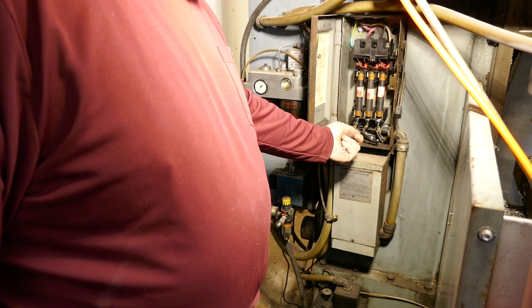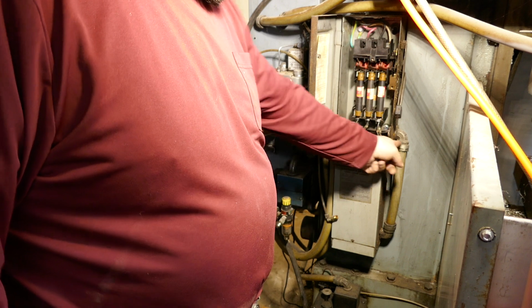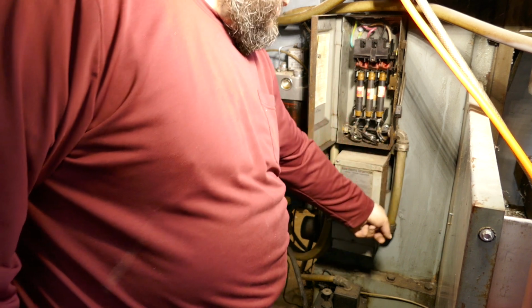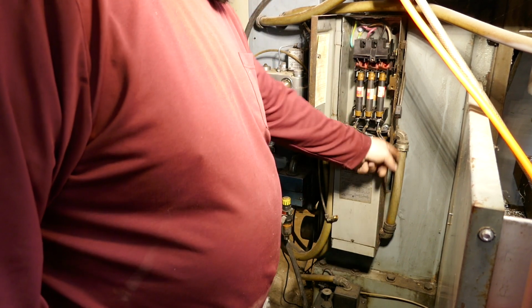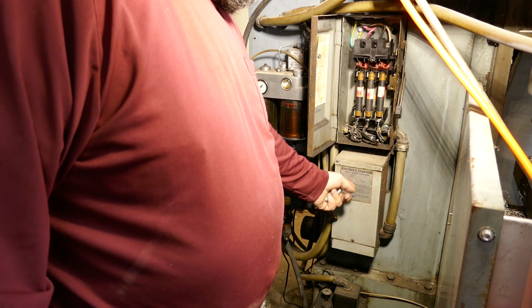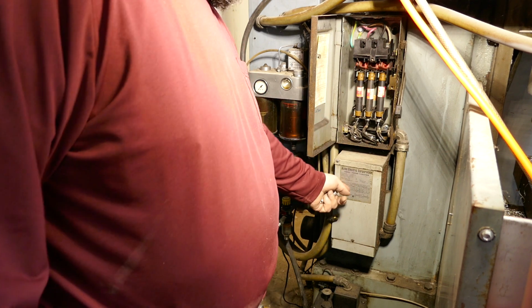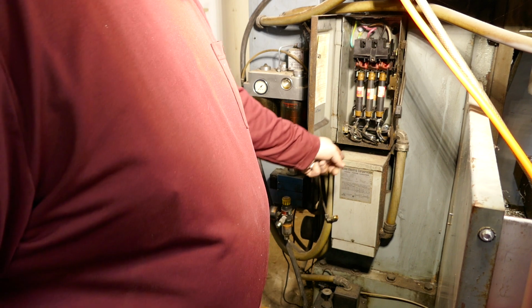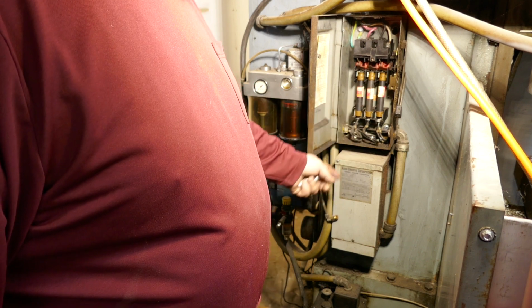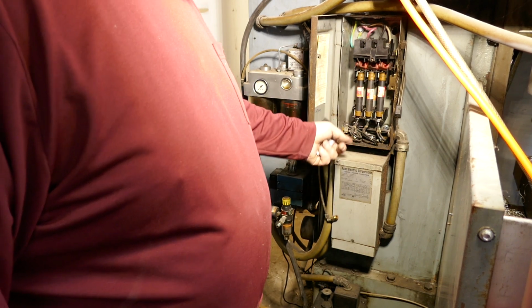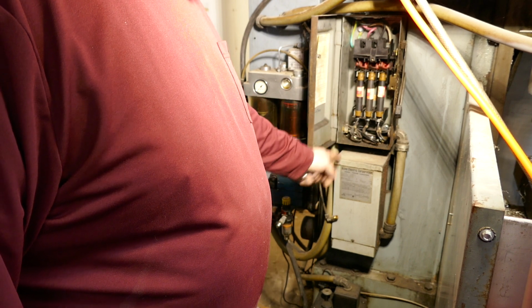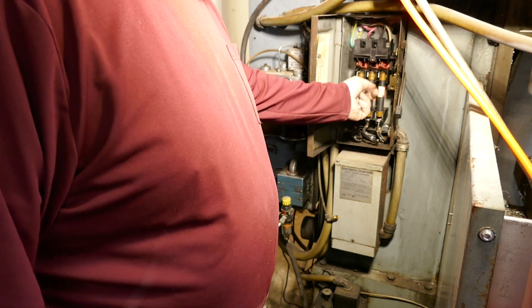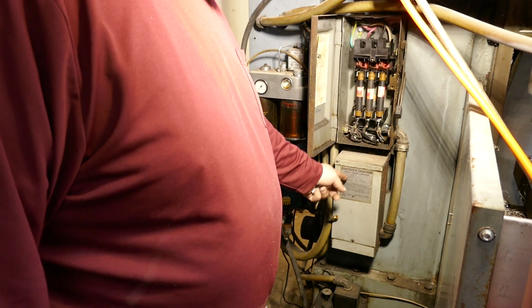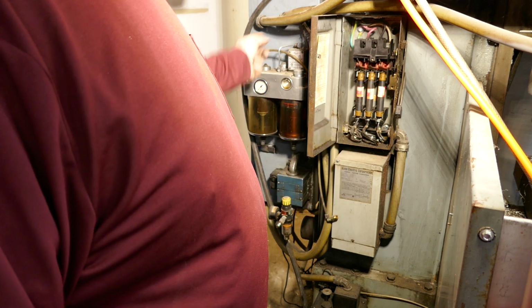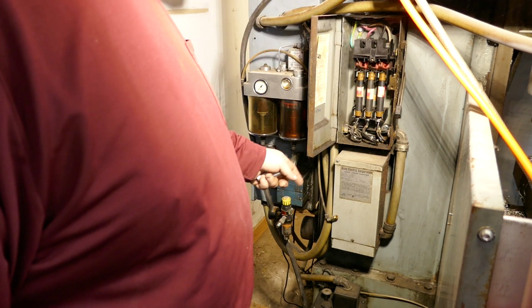Now, phases 1 and 3 go through this outside conduit down to this transformer right here, and then back out. So this transformer is a 240 to 120, a buck boost transformer used in bucking. This transformer takes the 240 that comes in, turns it into 120, feeds it back through, and then provides 120 volts to the control.